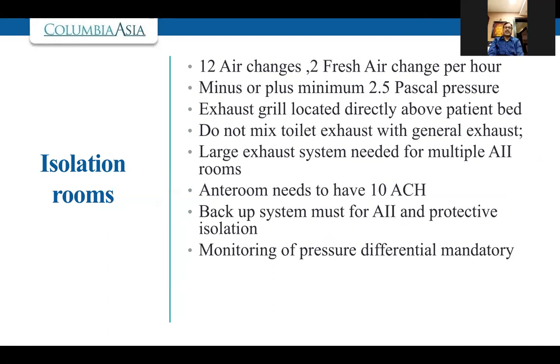These are all minimum requirements, mind you, friends. It is not the maximum requirement. So many times people go and object why it is showing 6, why it is showing 8 pascals. That need not be done, because this is a minimum requirement. If it is going below this, then we should object, saying that it has to be maintained properly. Most of the time the pressure changes are because people do not maintain their exhaust grills appropriately. A lot of dust settles there, and if you clean your exhaust grills, I think everybody can achieve the positive pressure as well as negative pressure which is required. A toilet exhaust should not be mixed with this exhaust. That one must remember. And the anteroom needs to have different air changes. But these are all ideal requirements.